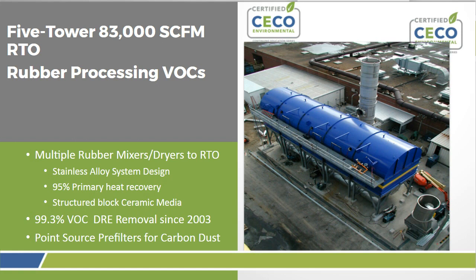Also, as Brendan mentioned earlier, you may need pre-filters on some applications. There's carbon dust in this application, a tough application in rubber processing. So know if your application does have dust, RTOs will make great filters. They really do, but you don't want to change that filter media, which is the ceramic media. It can be expensive and time consuming. So if you do need point source filters upstream, certainly do that.